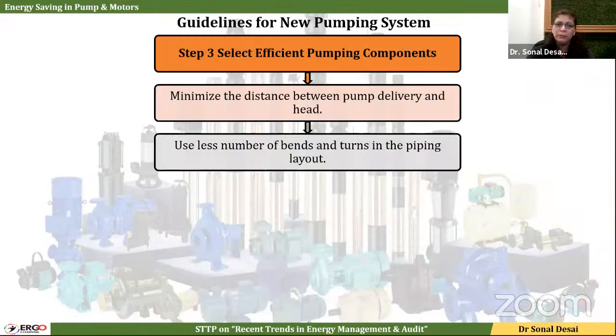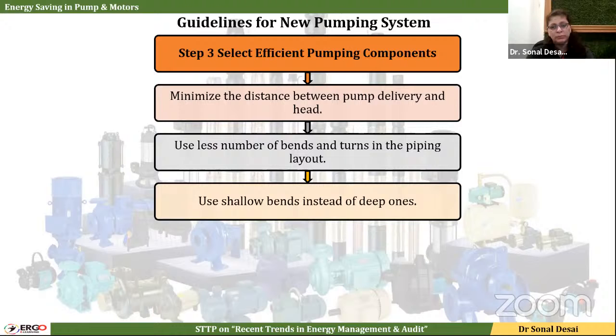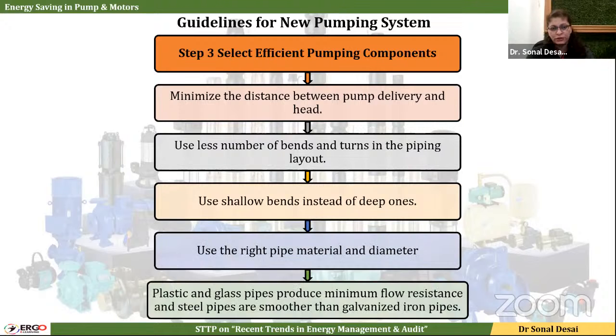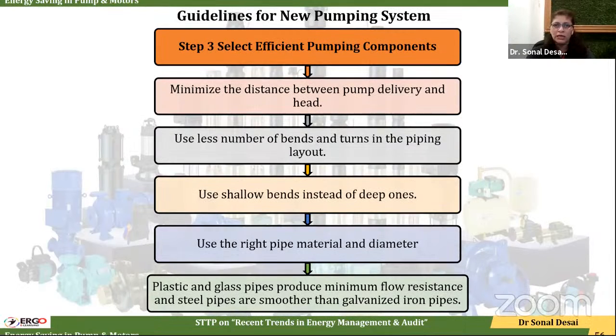Select efficient pumping components between pump and the source. Use fewer bends, use shallow bends, use the right pipe material which has less friction. Plastic and glass have minimum flow resistance. Steel is even smoother compared to galvanized. So these are the thumb rules to remember.